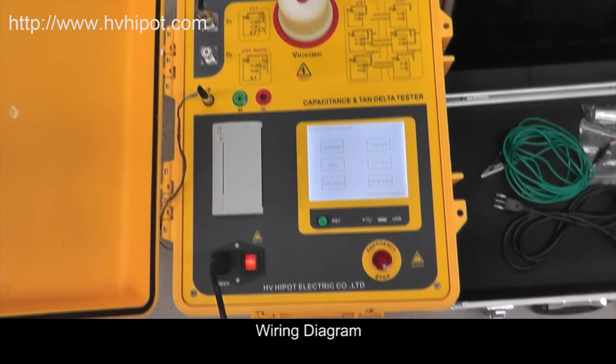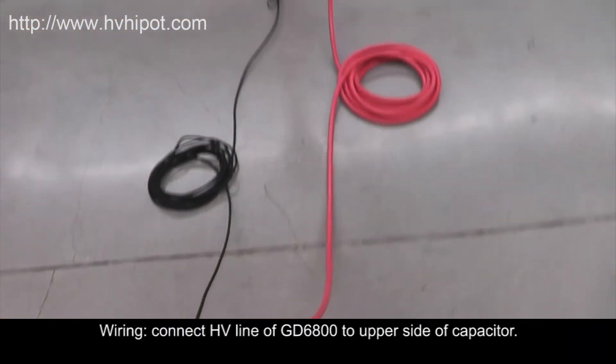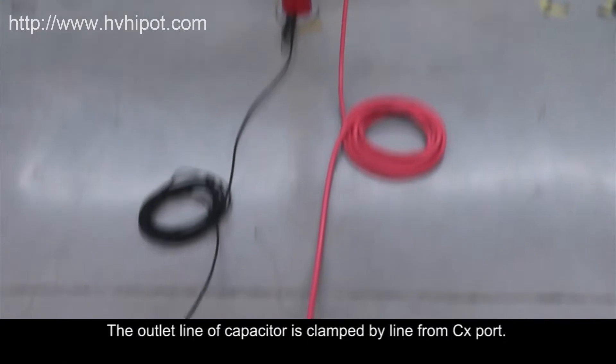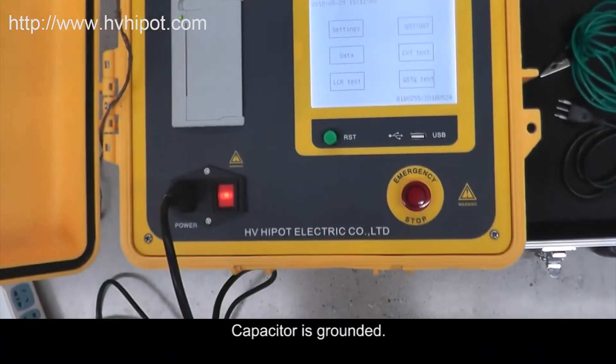Test 1, UST mode wiring diagram. Connect the HV line of GD6800 to the upper side of the capacitor. The outlet line of the capacitor is clamped by the line from the CX port. Note that the clamp cannot touch the ground, as the capacitor is grounded.